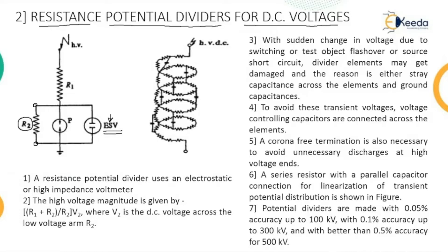A resistance potential divider uses either an electrostatic or high impedance value voltmeter. The high voltage magnitude is given by the equation: (R1 + R2) / R2 multiplied by V2. This means whatever voltage we have to measure, it is applied across this terminal — a high DC voltage is applied to this particular terminal, and we get the voltage with respect to the ground terminal.